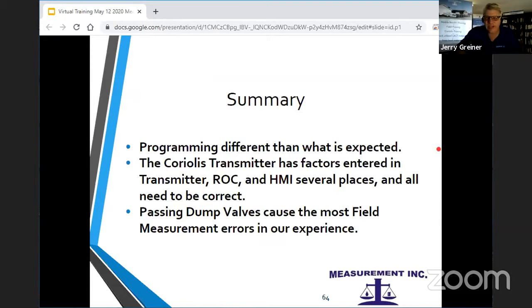For example, the Coriolis, it's programmed in pulses per kilogram instead of pulses per volume unit. Things like that are different than expected. In a Coriolis transmitter, there's several different places you can have meter factors. They all need to be correct in all the different places. And typically we'll put a tag on and say right on the tag where it's programmed. It's not wrong to program it in any of the different places.